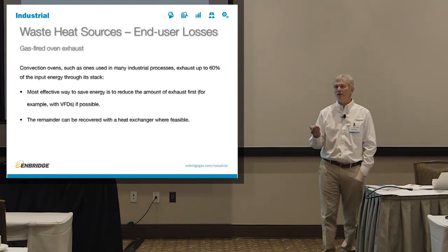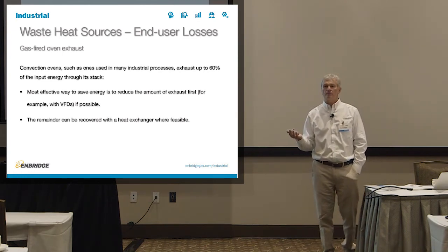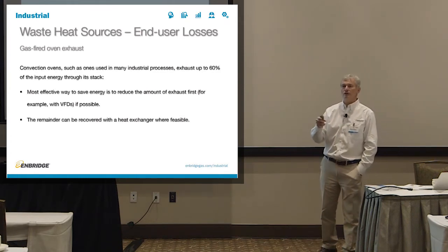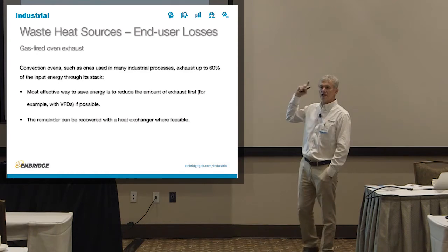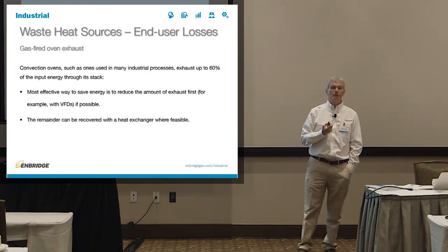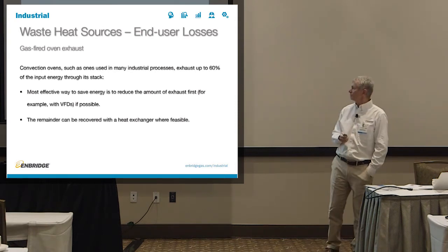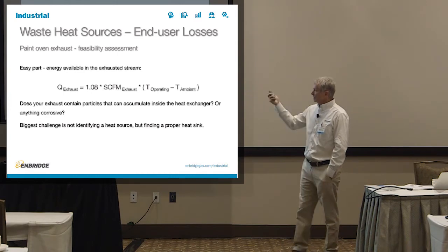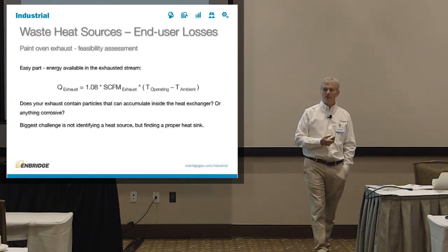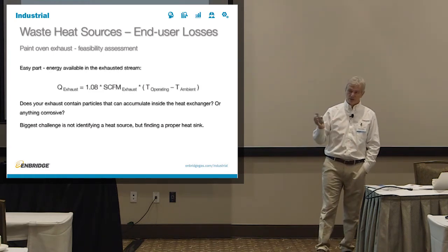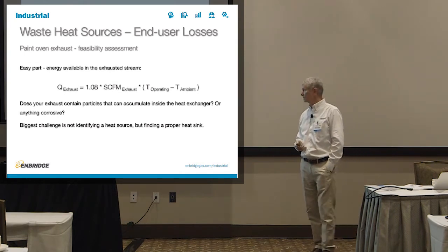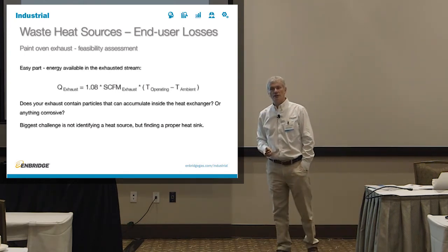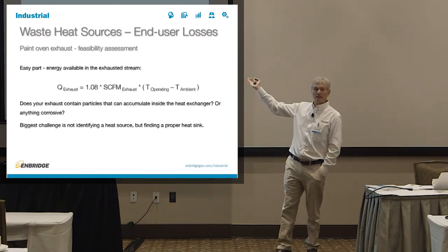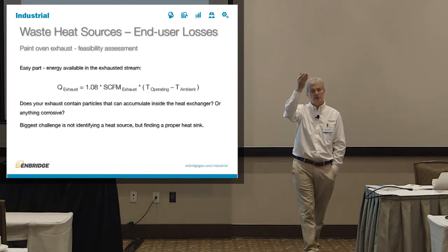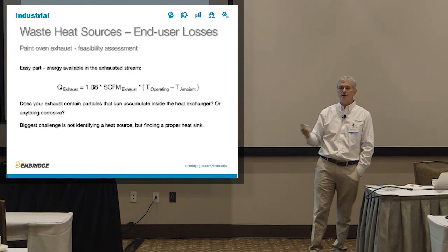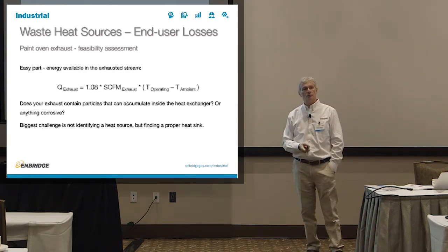There we go. So 5 million BTU burner, 1,000 CFM. But most of you, if you go back to the convection oven in your facility and look at the numbers, will have anywhere between 3 and 6,000 CFM exhausts. This is how you can calculate the energy in the stream: 1.08 times CFM times delta T. Regardless of what kind of airstream it is, this is the energy that you invest into that airstream. So if you have 5,000 CFM of exhaust that you don't need, delta T is usually 350, 370 degrees F operating temperature, 70 degrees ambient, so 300 degrees. So 5,000 times 300 is your basic energy that you're wasting every hour.